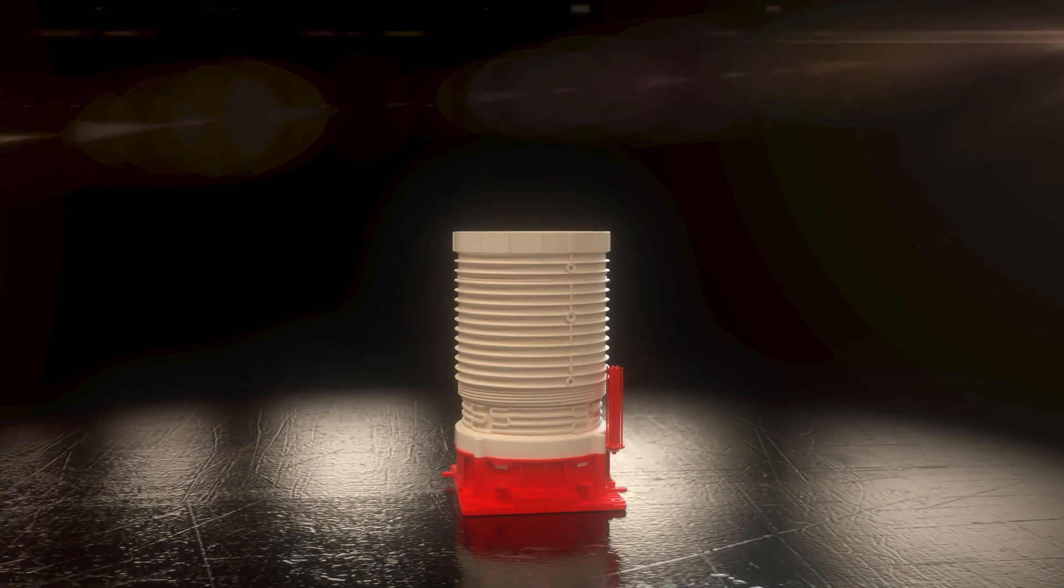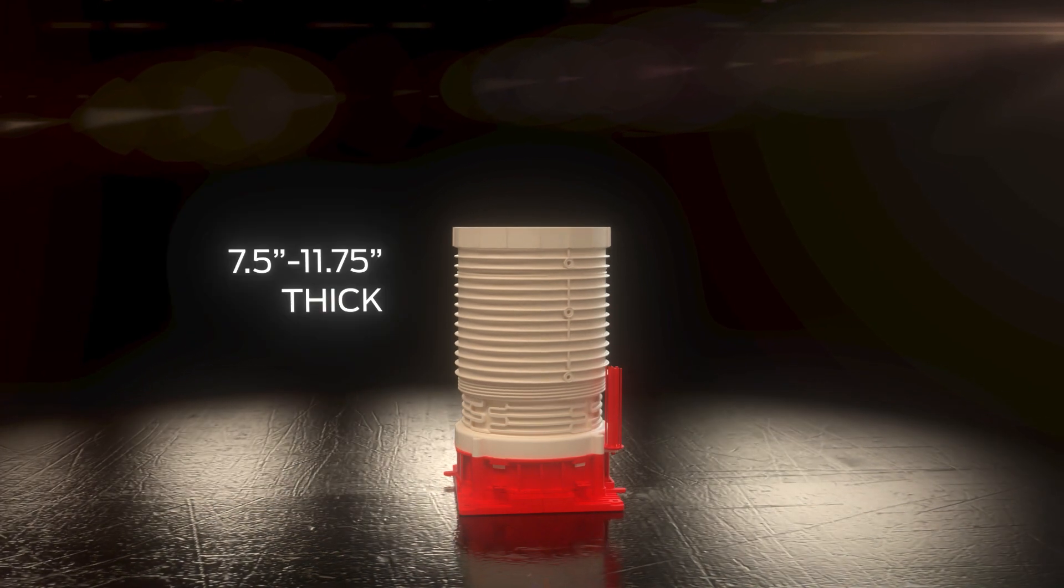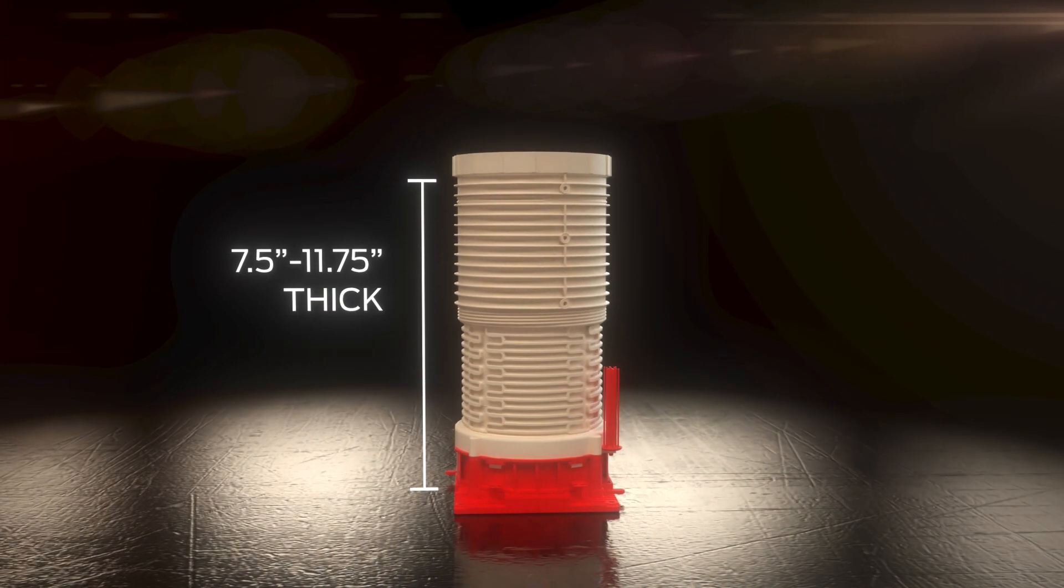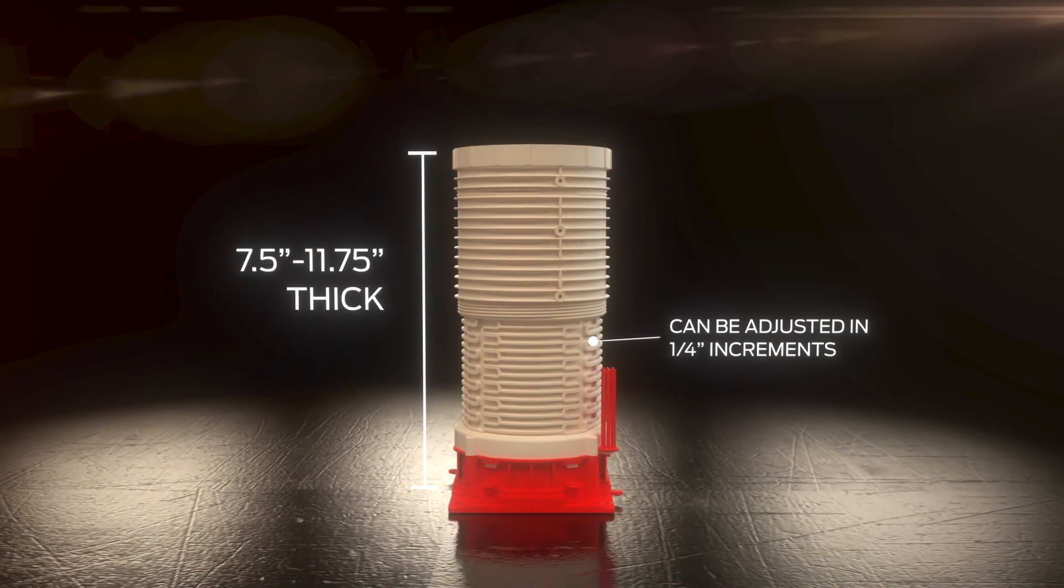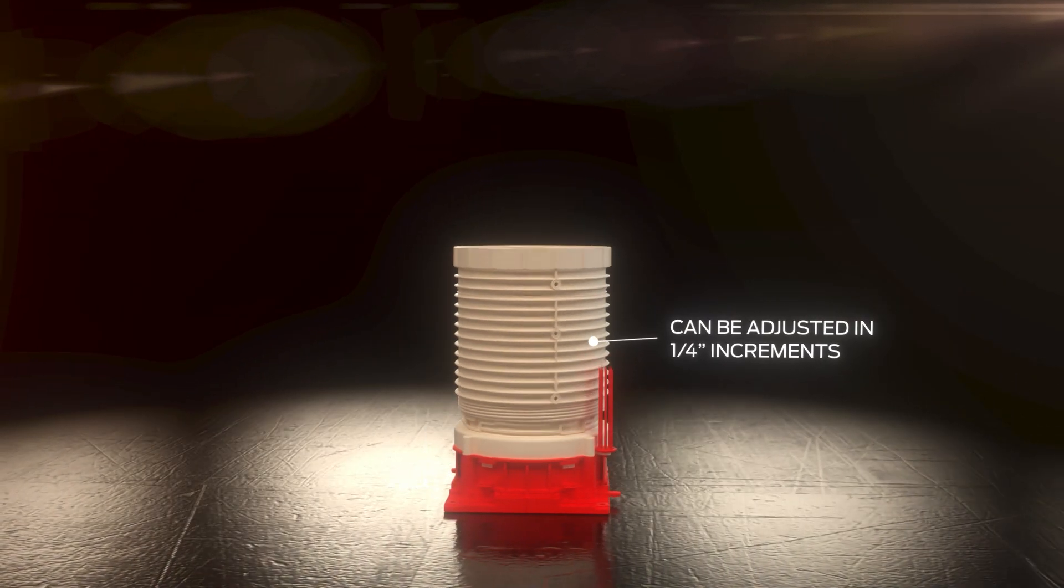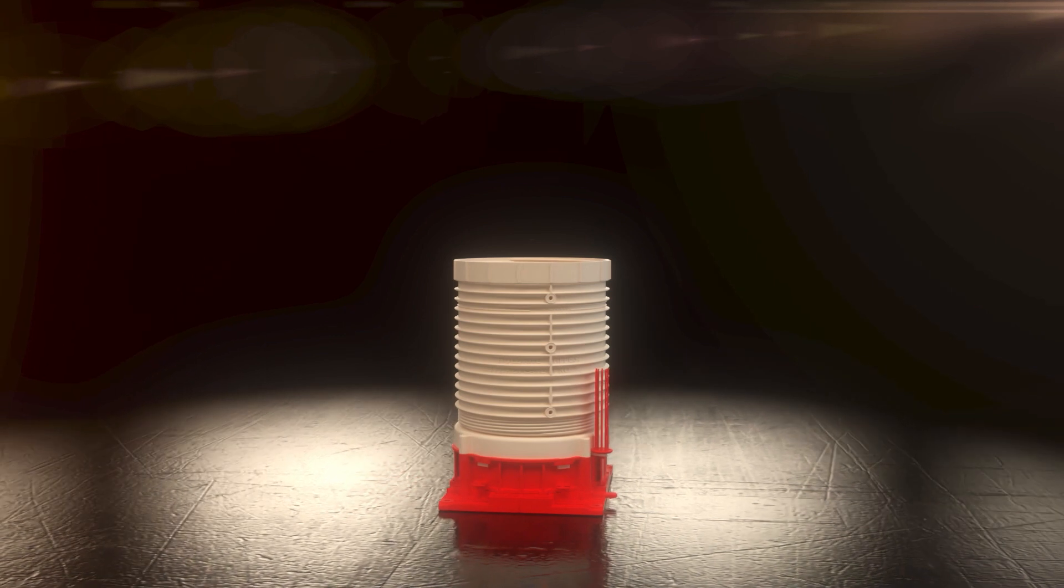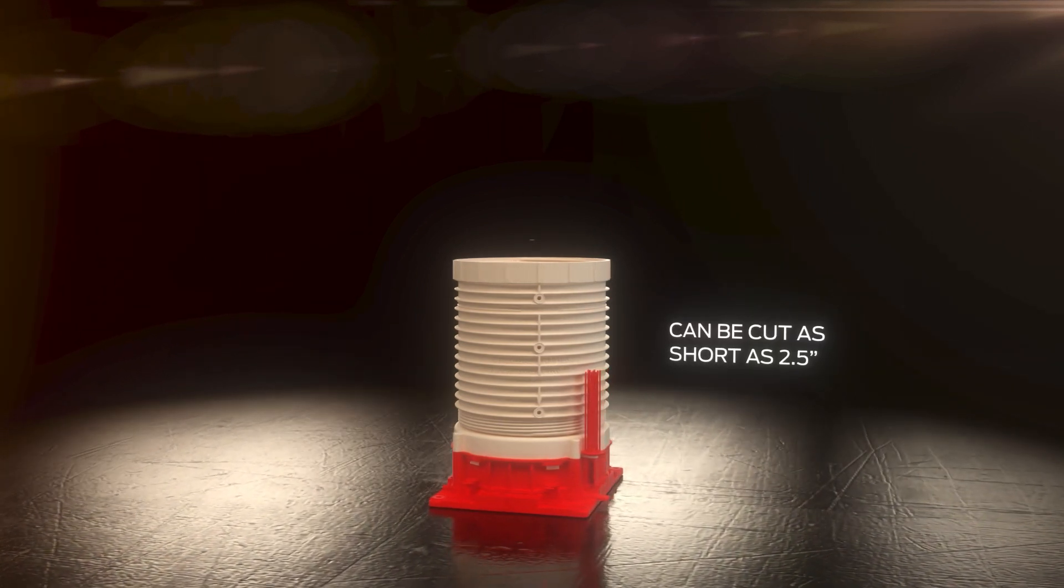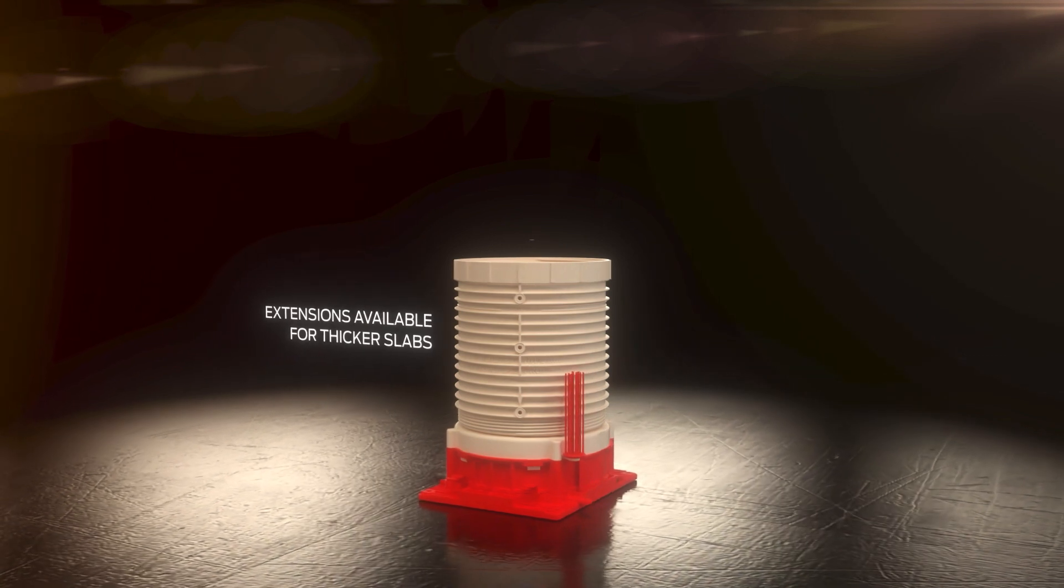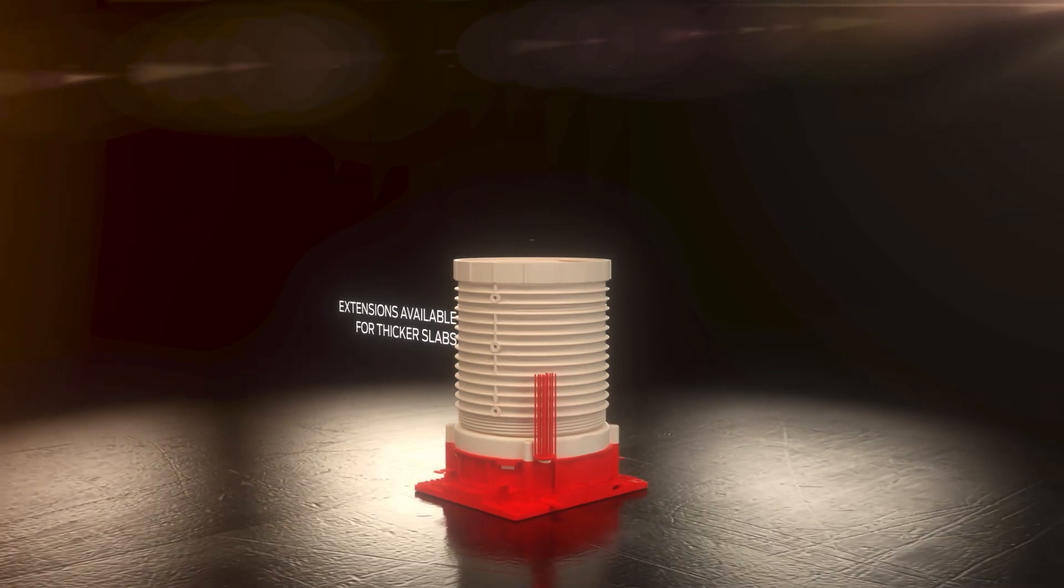The Hydro Flame Pro has a telescoping design that provides flexibility for slabs from 7-1/2-inch to 11-3/4-inch thick and can be precisely adjusted in 1-quarter increments. The sleeve can even be cut as short as 2-1/2-inch for thin corrugated metal decks, and extensions are also available for slabs thicker than 11-3/4-inch.